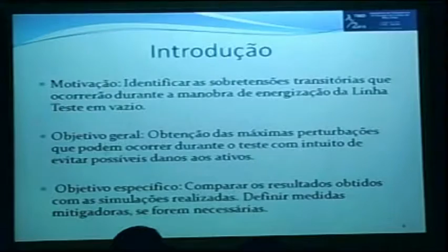transient overvoltages that may occur during our half-wavelength line maneuver. So, to get the main disturbances that might occur during the test, with the purpose of avoiding possible damage to the transformer, the generator, and the circuit breaker. The idea is to compare the simulation results to the test in the end, and identify in advance what the mitigation actions would be.